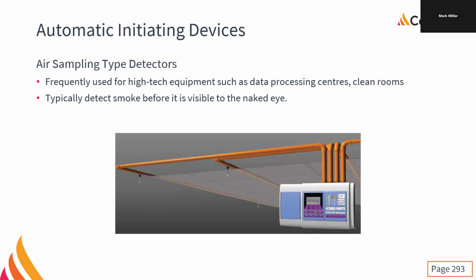because the piping and the sampling tubes and the holes and all that gets installed in the area, but the actual VESDA unit, right, the air sampling unit, can be installed in a different location. We just run the piping over to it. It's sealed piping. We're not getting any air in from anywhere else.